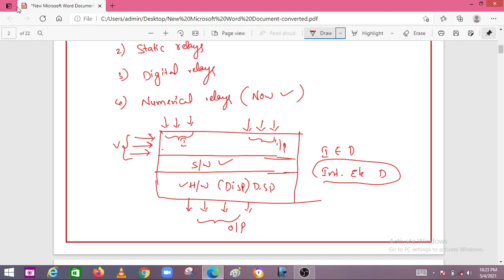So why do we require relays? Whenever there is an abnormal condition existing in the circuit, in the power system network, somebody has to sense that abnormal condition, and somebody has to break the circuit, so that the generator or transformer or any equipment connected to the transmission system or power system is protected. As we discussed, the breaking and making of a circuit can be done by using a circuit breaker, and the intelligent part of this protection system is taken care of by the relay. So the relay has to sense that abnormal condition first.